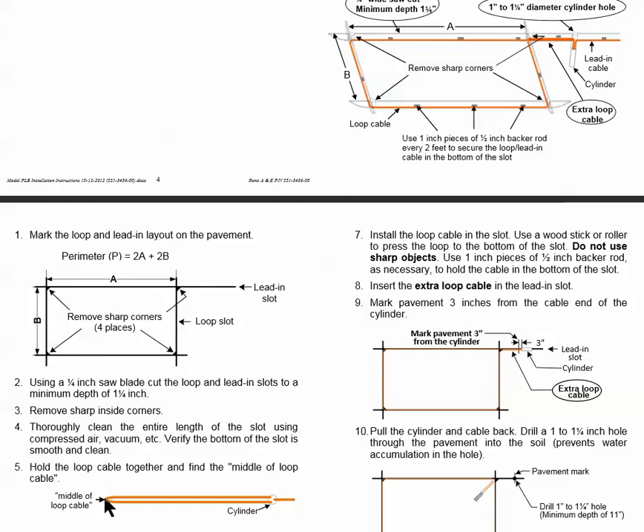And also placing in step five, placing the loop into the saw cut. Don't push it all the way in at first. Inspect again for any sharp edges on the corner and carefully push it in just a little bit so that you can see that when you get to this point where the loop comes together and heads out to the point where the cylinder drops into the hole that the wires don't bunch. So don't commit to anything until you feel comfortable that everything is just perfect. And then just use a soft tool of wood or some kind to push the wire into the saw cut. And don't use screwdrivers or anything with sharp edges.